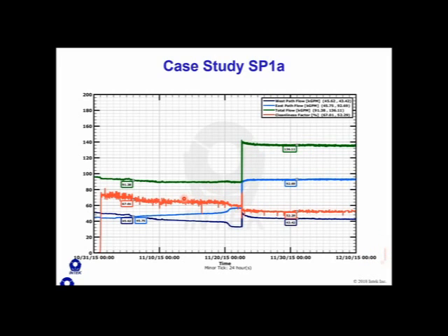So as I mentioned, the cleanliness factor shown in red started at 70%, and so I'd like to ask, what do you guys see in this data? Go ahead and respond in the question box, okay? When this unit comes on, I think you would expect to see the performance factor come up and stay flat.